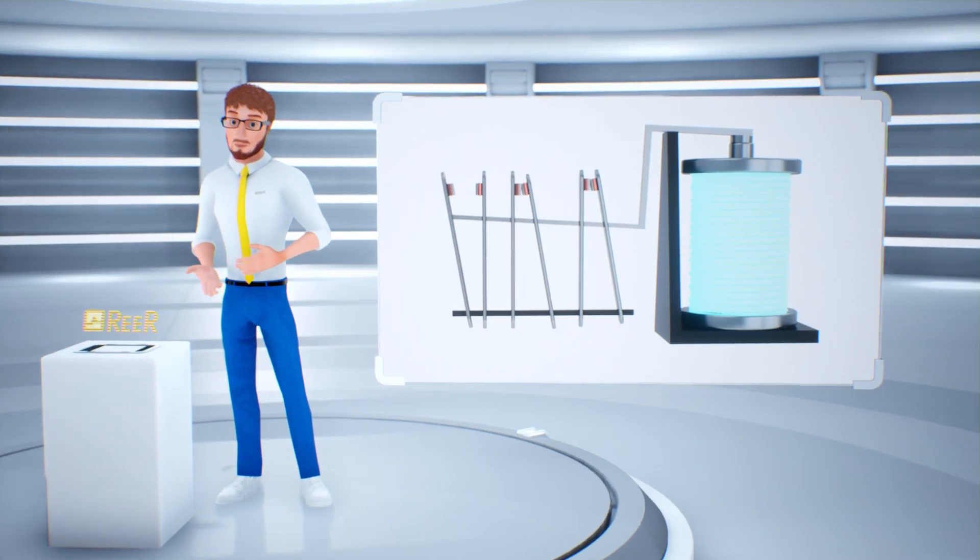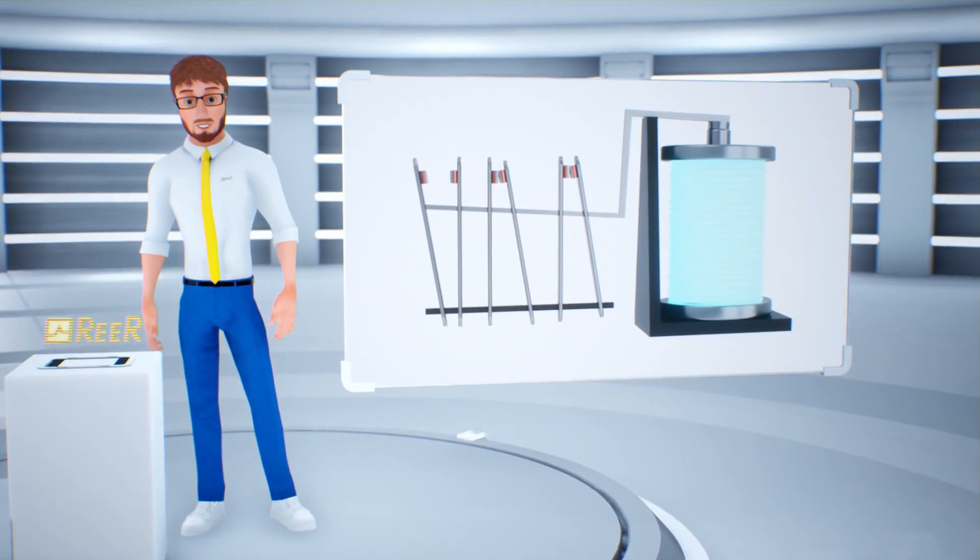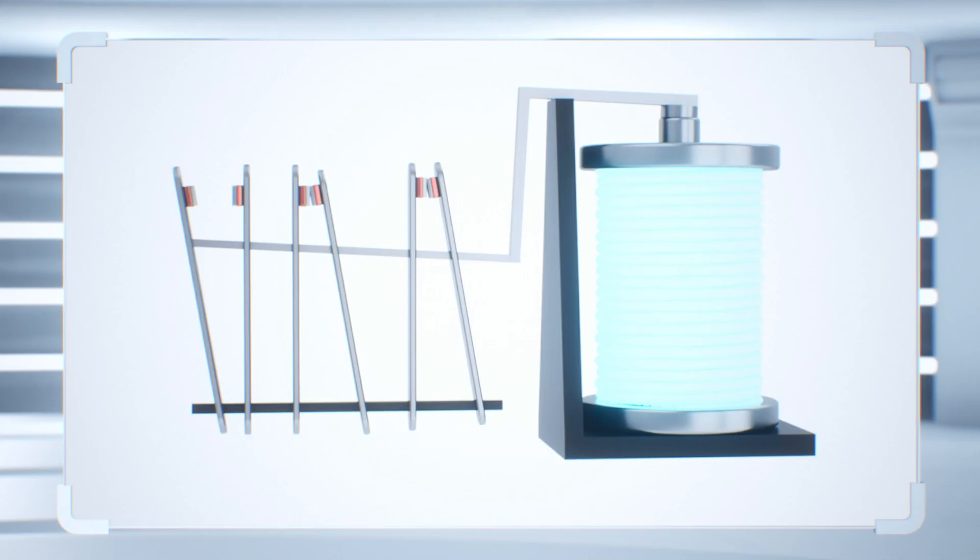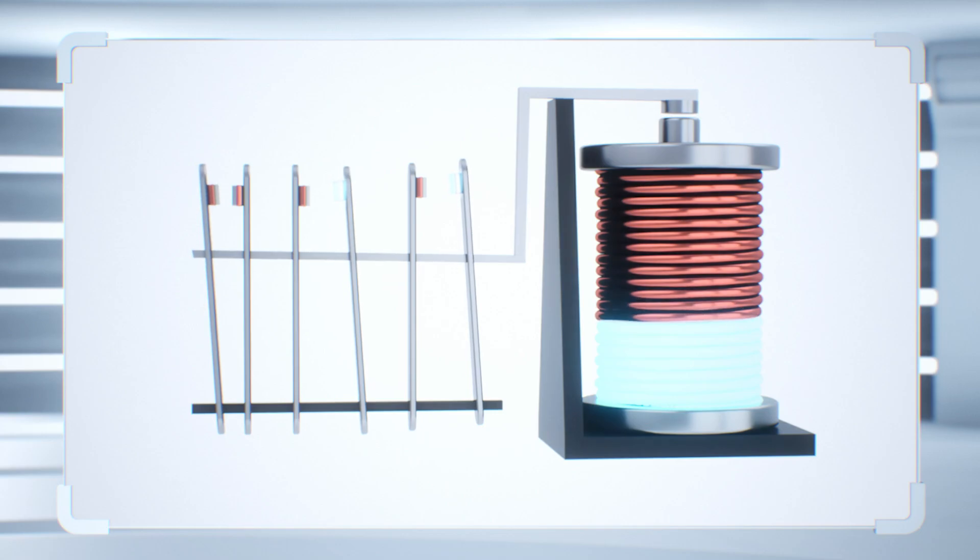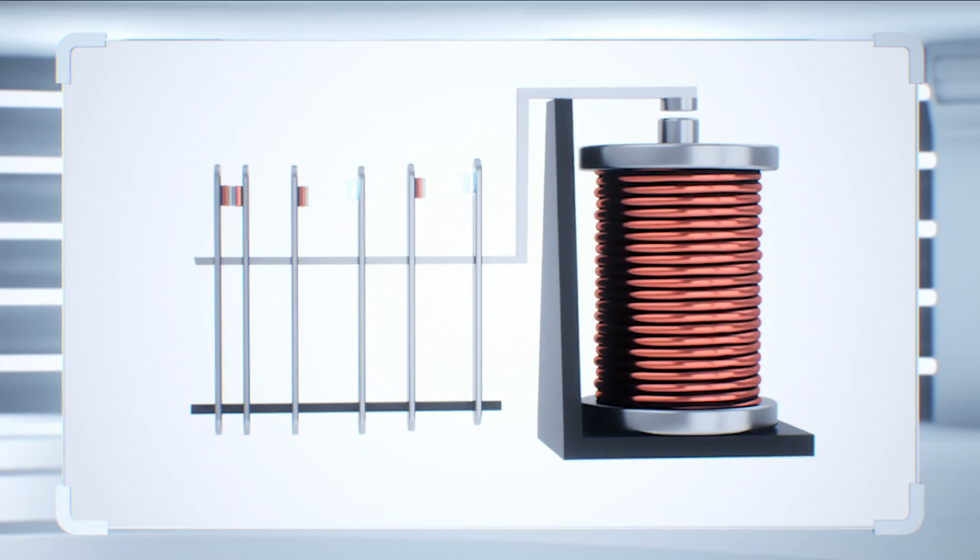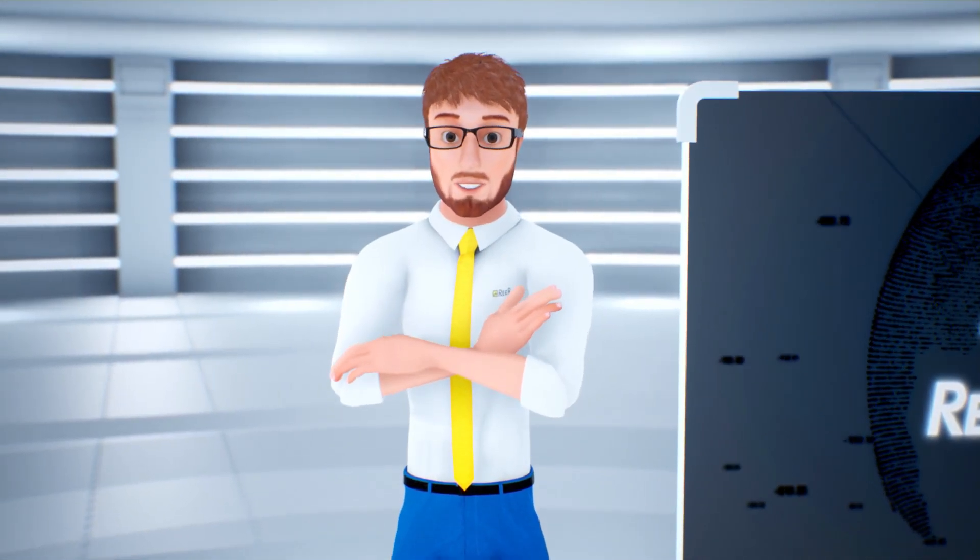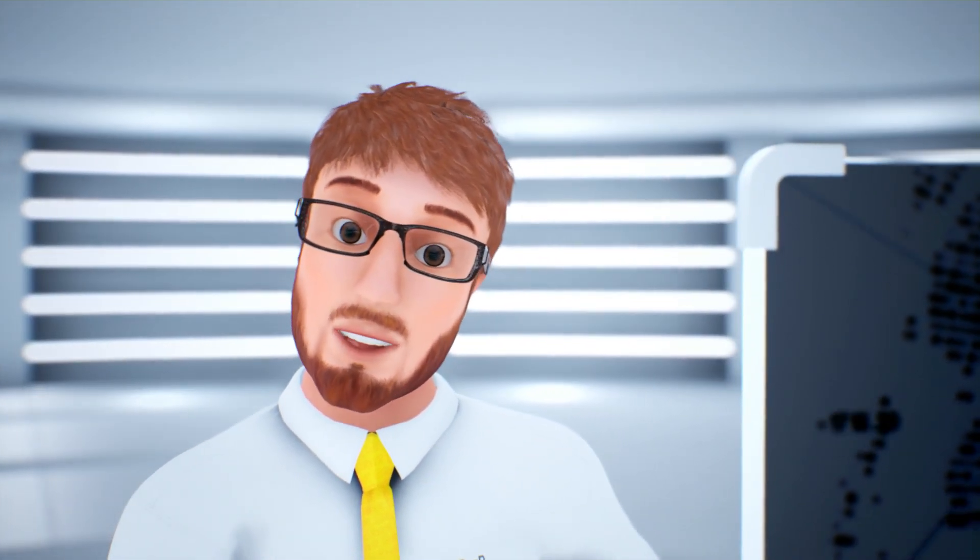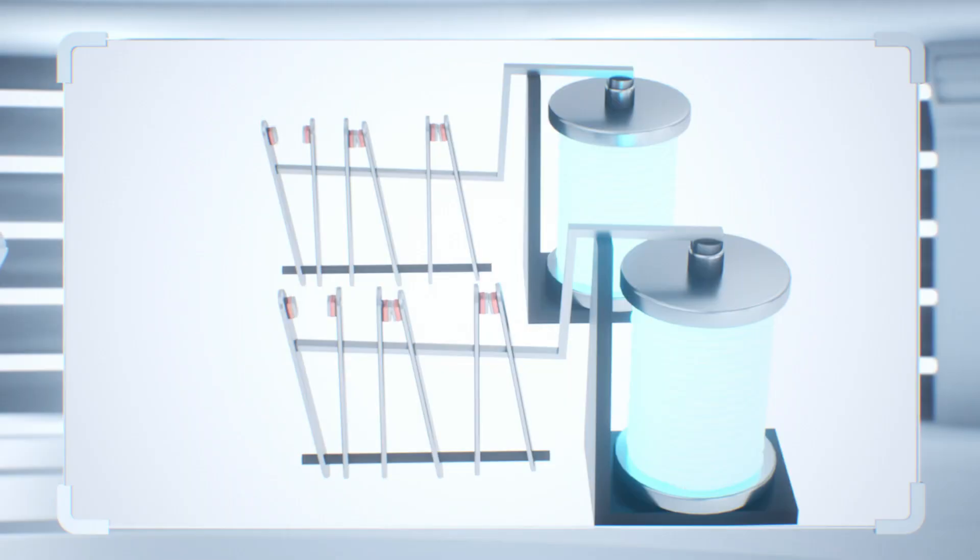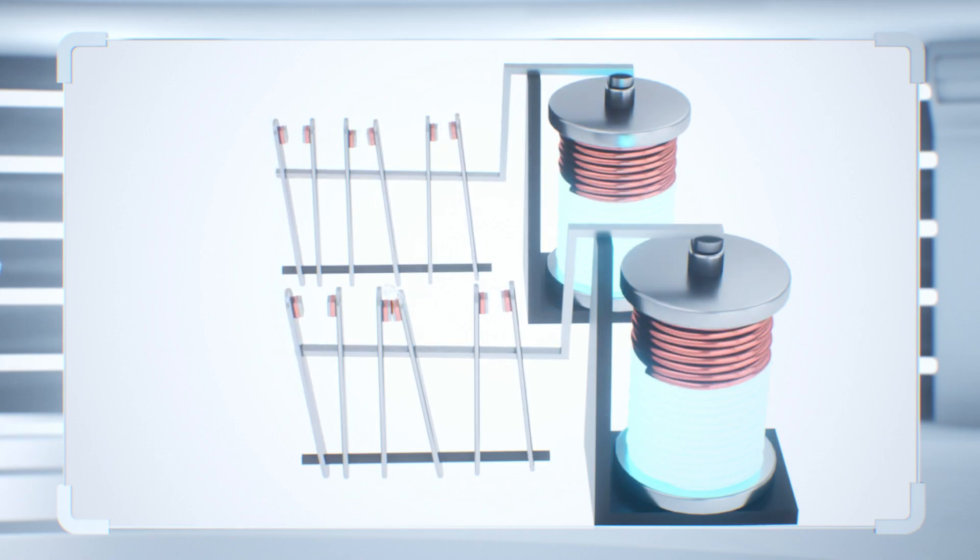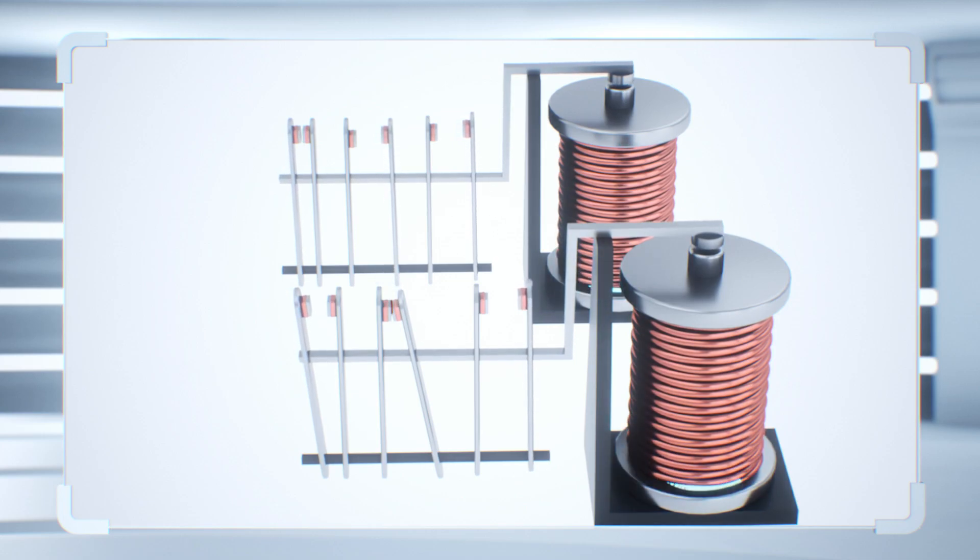To safely stop the operation of a machine, for example, the power supply is interrupted by two different contacts. Both of them then open and come back to their normal positions. To reach the highest safety levels, for example PLE, the machine directive implies that a redundancy circuit is always used. Therefore, two safety relays are used, and even if one of the two would break, the other would still open the safety circuit.